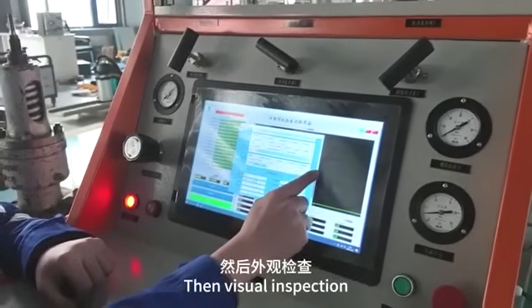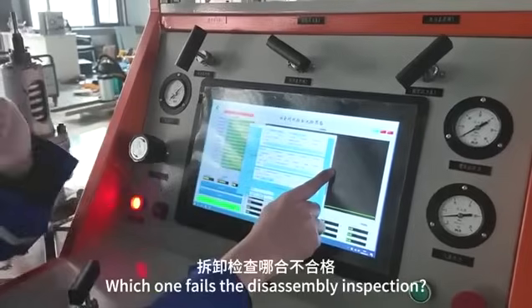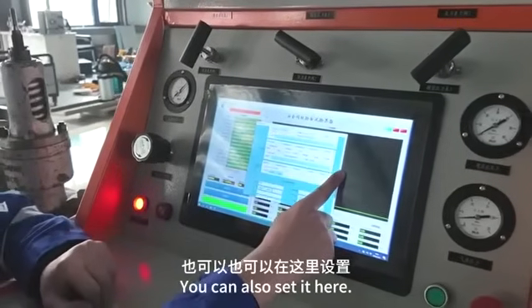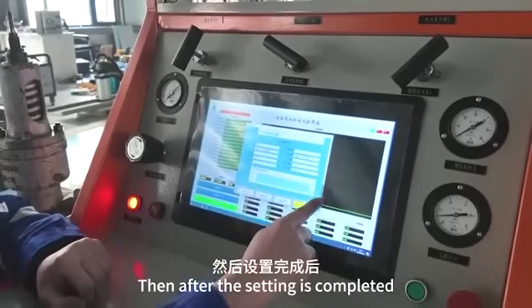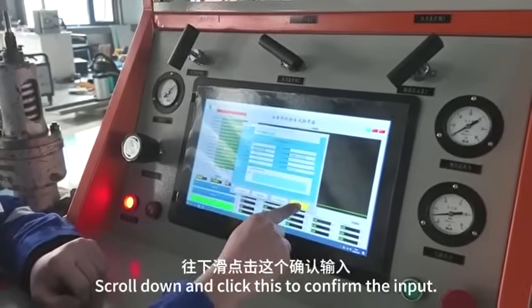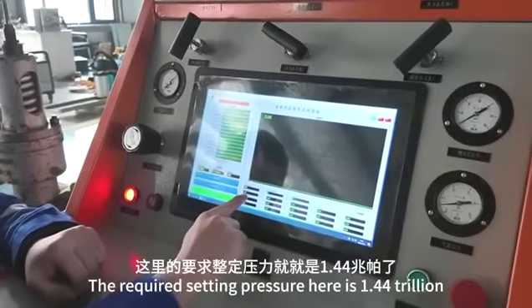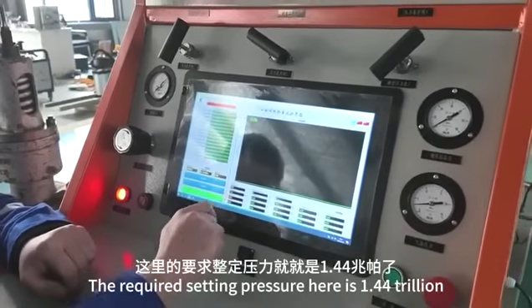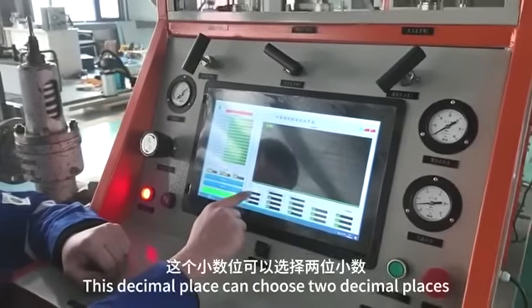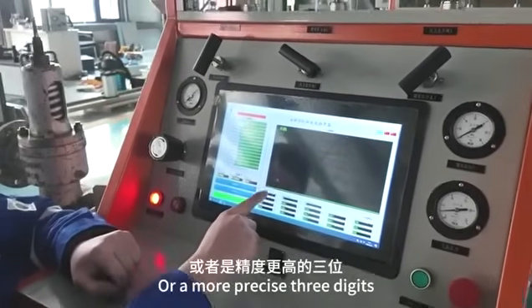Then visual inspection. Which one fails the disassembly inspection? You can also set it here. Then after the setting is completed, scroll down and click this to confirm the input. You can see it. The required setting pressure here is 1.44 MPa. This decimal place can choose 2 decimal places, or more precise 3 digits.